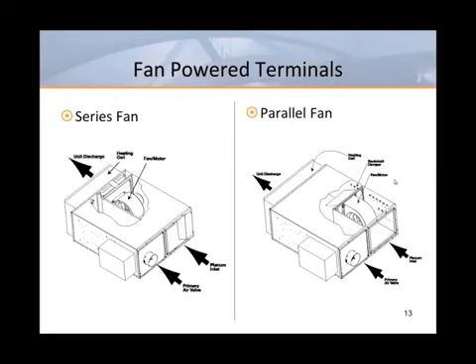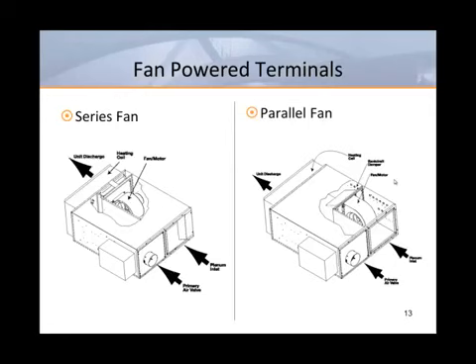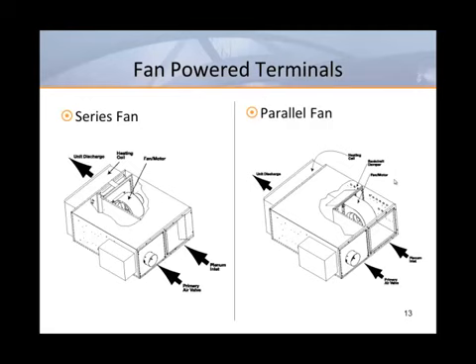The function and layout of a parallel unit is very different. In the cooling mode, the unit fan is off and the VAV inlet supplies cold air to the space just like a single duct box. When less cooling is required, the primary damper closes until it eventually reaches its minimum flow limit. If the room temperature continues to drop, the unit fan switches on to pull warm air and blow it out to the room, and if more heat is required, a hot water coil or electric coil is used. The blower in a series fan box must be sized larger to handle the design cooling air flow, while the parallel blower handles only the lower heating flow rate — so the series blower is typically twice as big. Since the parallel fan is off during the cooling mode, a backdraft damper is generally necessary to prevent the loss of primary air to the ceiling plenum, and this can become a point of leakage.